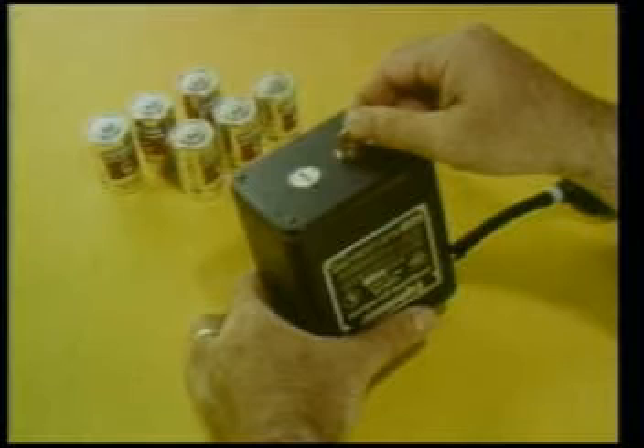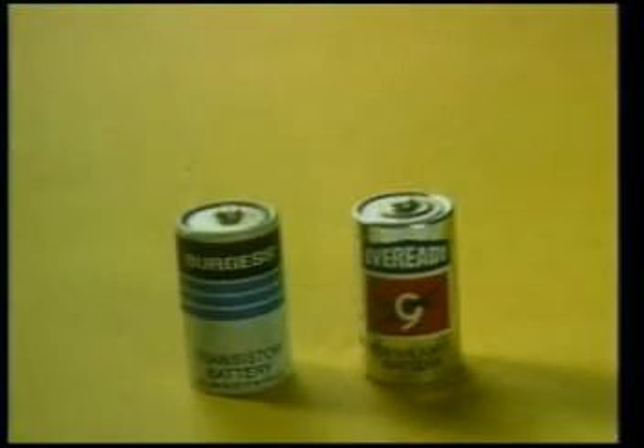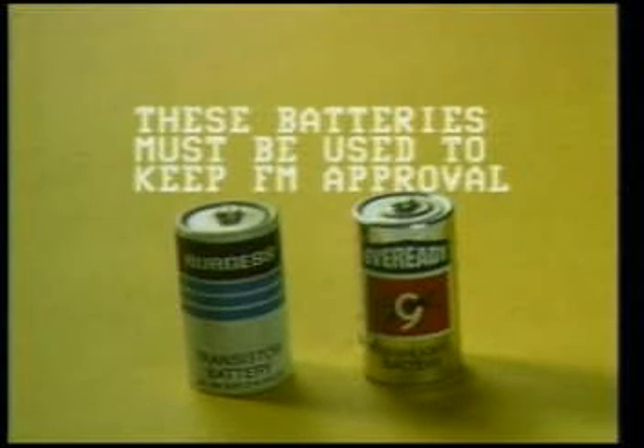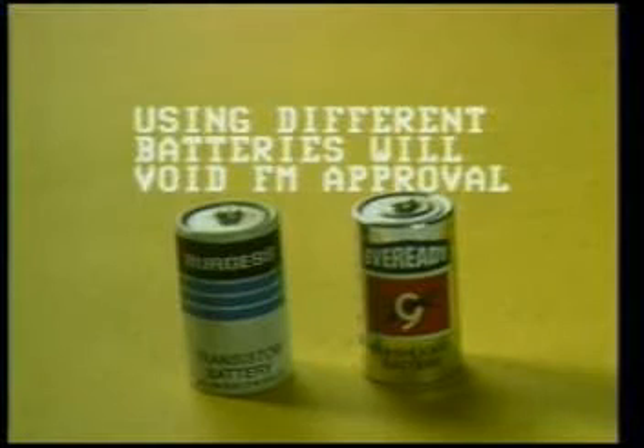To change the batteries, unscrew the 2 large screws on the bottom of the case. You'll note that the slots on the screws are extra large, so you can use a coin to open the case if batteries need to be replaced in the field and a screwdriver isn't handy. The explosimeter indicator uses 6 D-size flashlight batteries. They should be replaced with Burgess or Ever-Ready batteries only in order to keep the factory mutual approval for use in hazardous atmospheres. Although other batteries will work, the approval is void because only these 2 brands have been tested for use with the instrument.